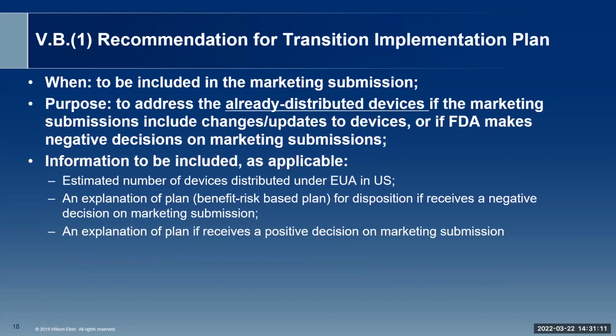Section V, subsection 1, the FDA recommends including in your marketing submission a transition implementation plan. This is very similar to what we talked about, the risk mitigation plan, except that you have to include this plan in your marketing submission. The purpose is, again, to address the potential risks of the already distributed devices once the EUA is terminated and you have not received a final FDA decision on your marketing submission yet. So during that vacuum period, your products are without any sort of FDA authorization or approval. How do you deal with the potential risks?